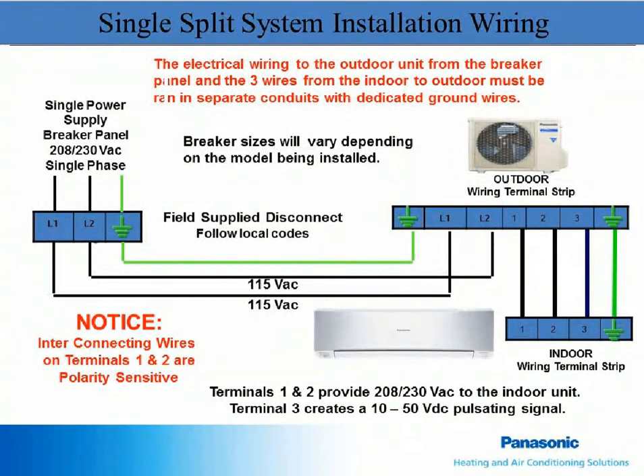All indoor units get their power from the outdoor unit. Run the power supply from the disconnect to L1, L2 inside of the condenser. The ground should run back to the panel and is highly recommended to drive in an additional earth ground also.